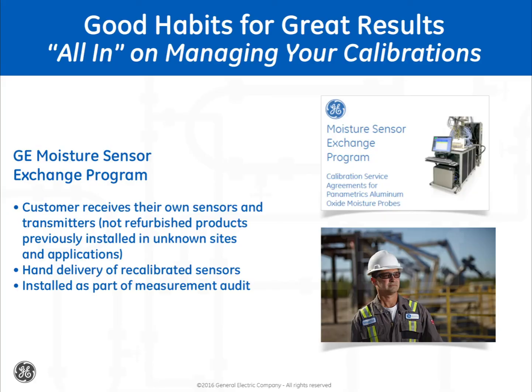The most impactful relationships occur when the vendor and customer agree on calibration schedules. The vendor manages the customer's spare sensor pool and sends the customer's recalibrated sensors to the plant in advance of the need. GE has the most success with the moisture sensor exchange program with our larger customers, especially those with a fair number of sensors in critical applications. We ensure that the customer receives their own sensors and transmitters. These are not refurbished products nor previously installed at unknown customer sites or applications.